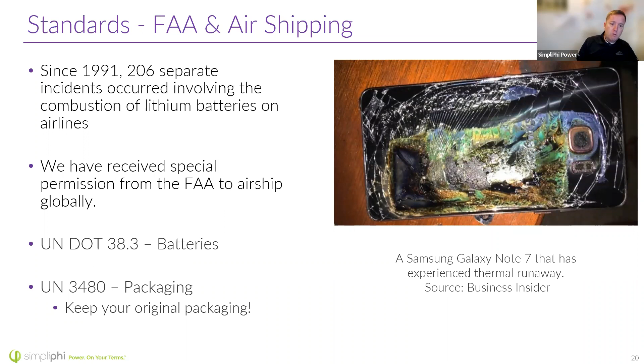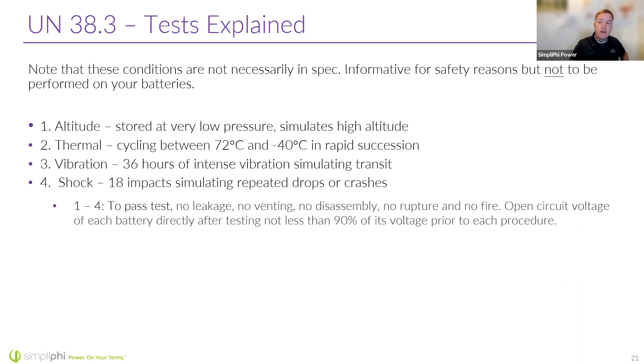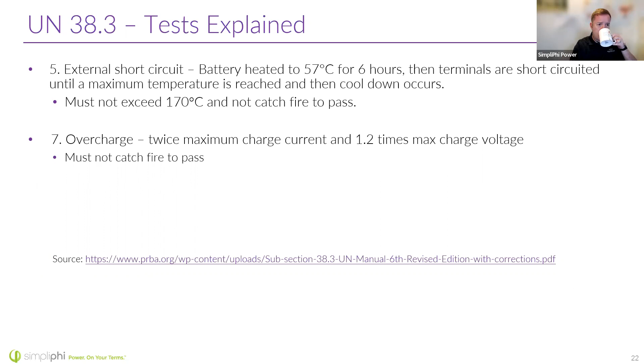We have the UN DOT 38.3 certification, which allows you to air ship these batteries. Part of getting that certificate involves exposing one of our batteries to situations it might see in the cargo hold of an airplane. When the plane's on the ground, it's pretty warm and air pressure is high, but up in the sky it's low pressure and becomes really cold. In the UN 38.3 tests, we cycle the battery between cold and hot temperatures, simulate vibration, shock and impacts. If the battery doesn't vent, leak, or catch fire, it can achieve this 38.3 certification for air shipping. They also short it out and overcharge it as part of the test.